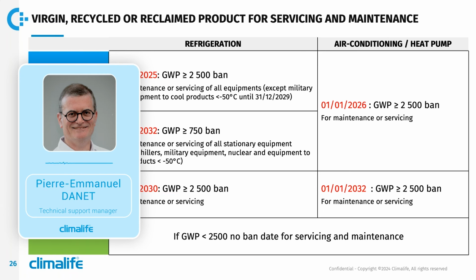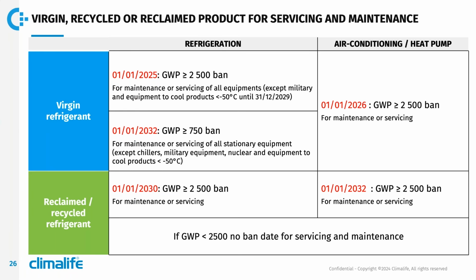Okay, now let's take a closer look at the dates for the use of new refrigerants, known as virgin, and reclaimed or recycled refrigerants, by activity. For the maintenance of refrigeration installations, virgin refrigerants with a GWP higher than 2500 will be banned from January 1st, 2025, except for what you can see on the screen. Then, from January 1st, 2032, the GWP will be reduced to 750 for maintenance.